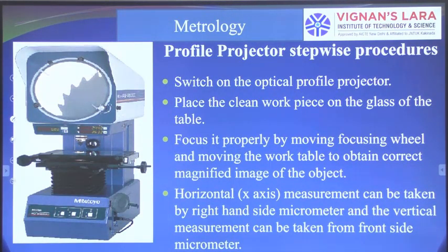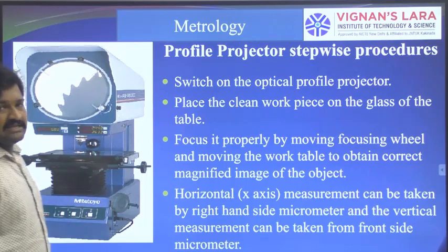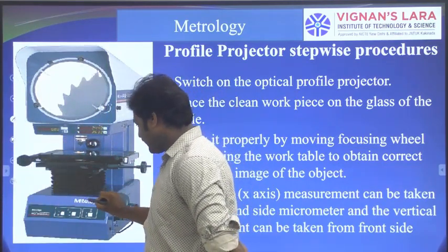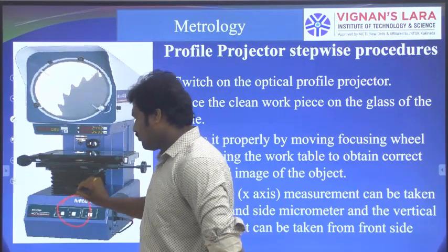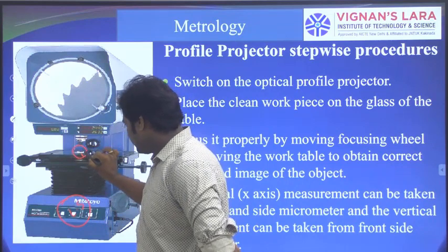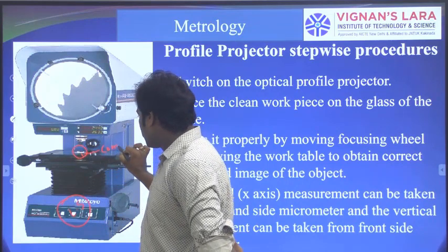Stepwise procedure for operating optical projectors. This is the component. As per the earlier principle, the light source is available here at the bottom of the component. Here is the light source, and after that we place our component or object here.